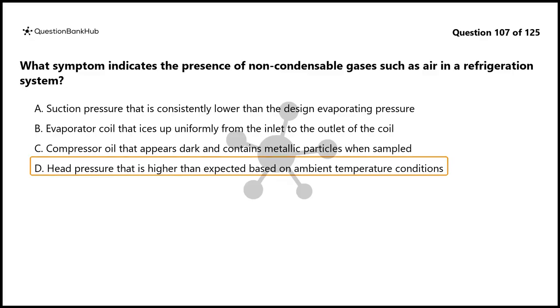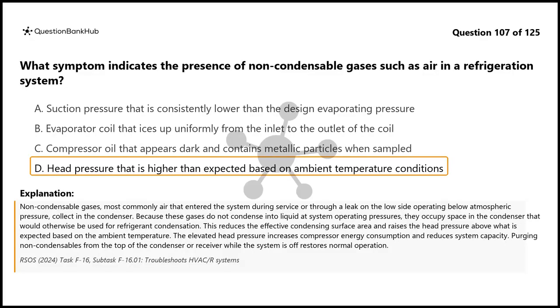The correct answer is D. Non-condensable gases, most commonly air that entered the system during service or through a leak on the low side operating below atmospheric pressure, collect in the condenser. Because these gases do not condense into liquid at system operating pressures, they occupy space in the condenser that would otherwise be used for refrigerant condensation.